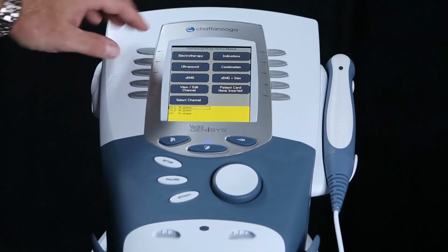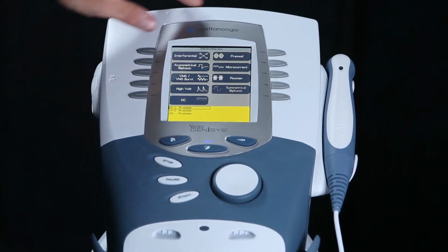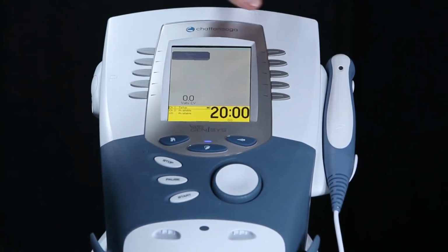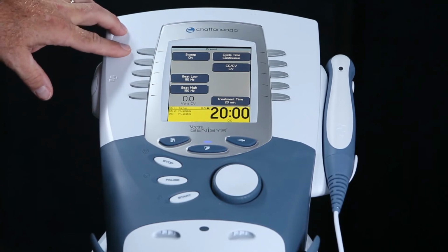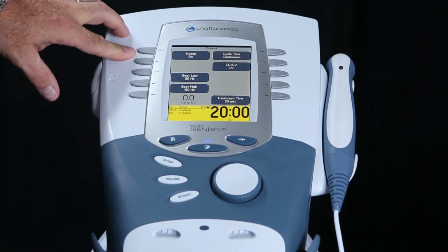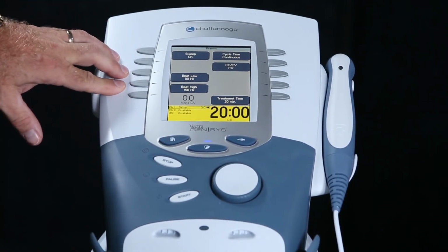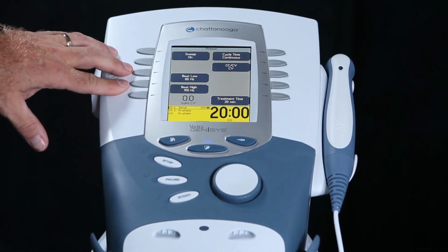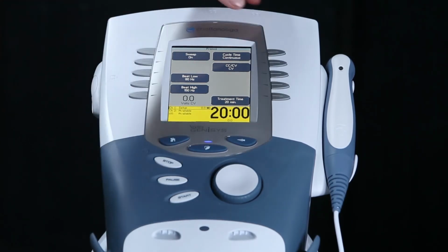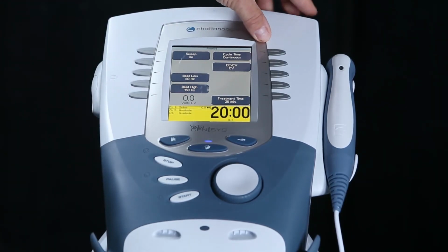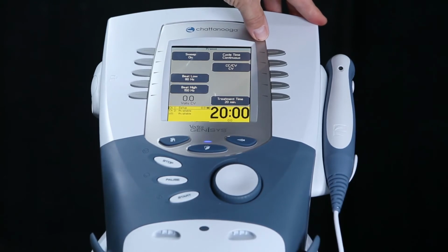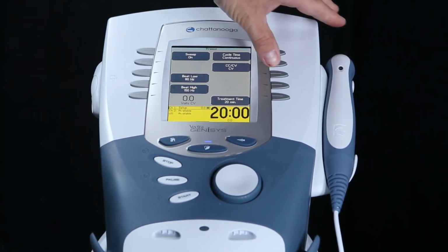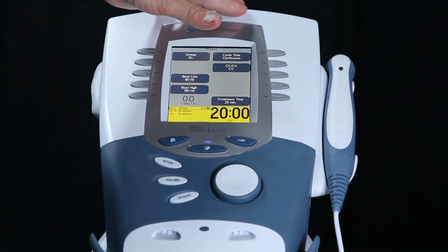Now let's press the electrotherapy key, then we'll press the Premod key, then we'll press the edit key to change our parameters. The first parameter, sweep, is set at on, that's where we want it to be. Our frequency is set at 80 and 150. We'll leave that there since we're going to use a gate theory protocol to treat this knee pain. The cycle time will be continuous and will be set on constant voltage. Since it is continuous, that will create a more comfortable treatment for our patient. Our treatment time is now 20 minutes.